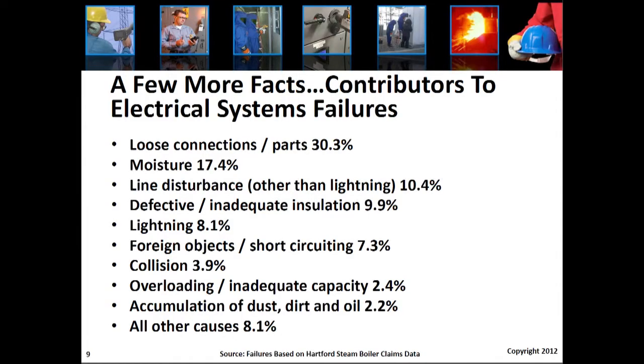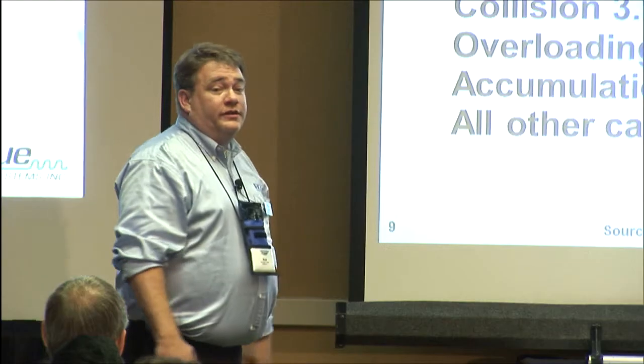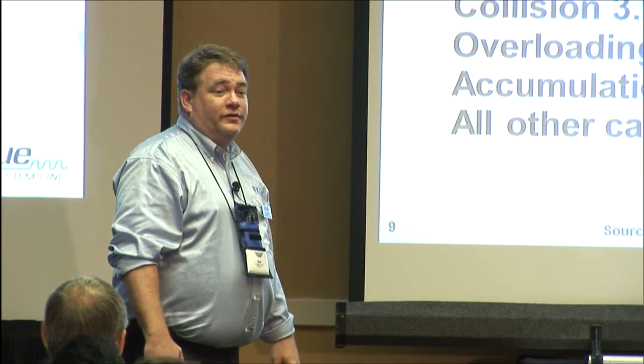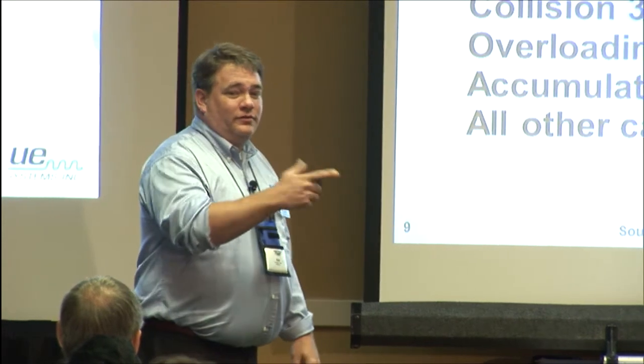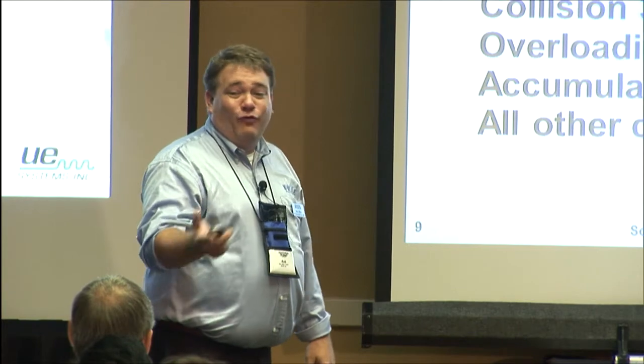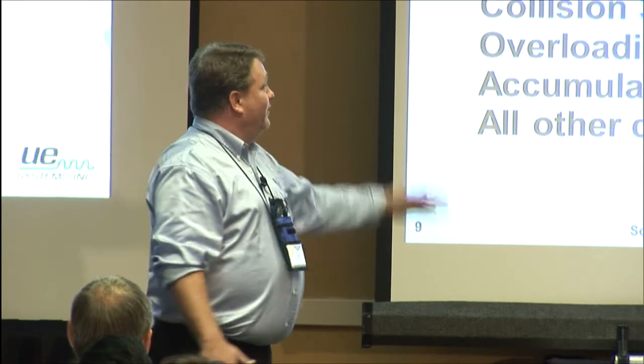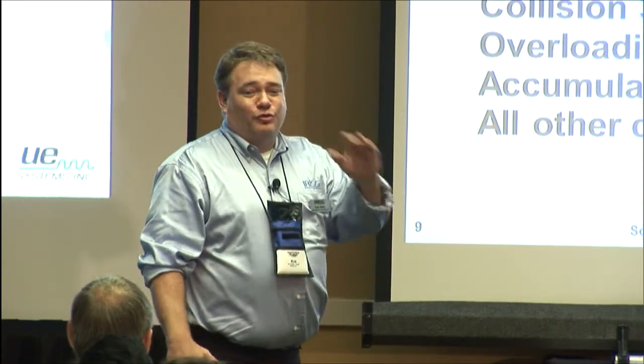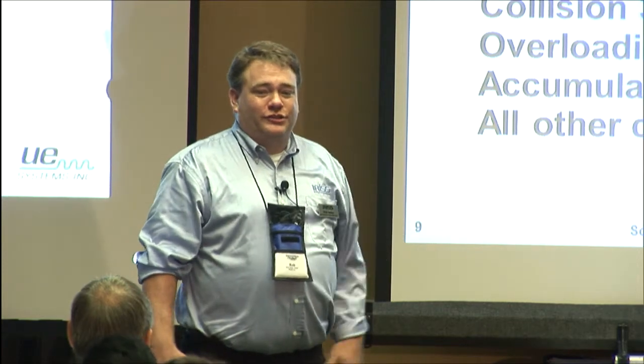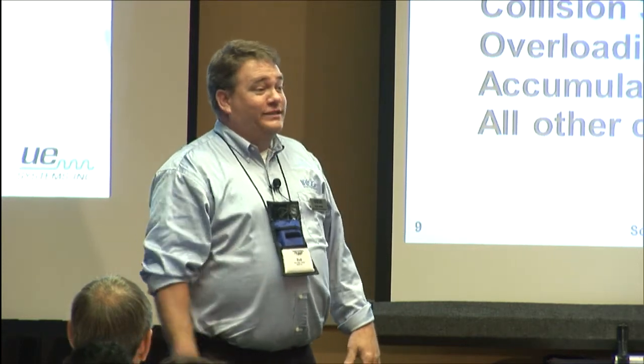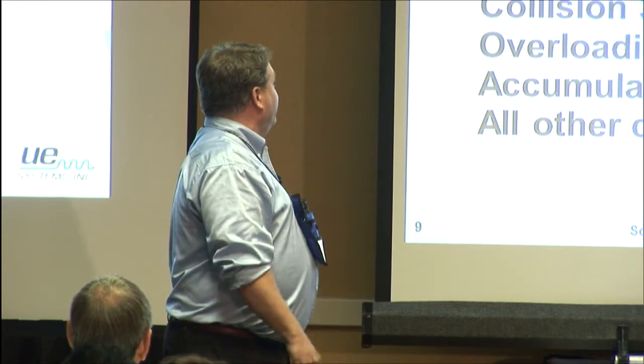A few more facts. I'll just tell you: loose connections, loose parts account for 30% of electrical failures. That loose connection can be found through arcing, tracking, corona, infrared cameras—all the things we're talking about here. If you went in and said, I can take care of 30% of the lost production in a facility, it's real easy to justify the cost of the technology.